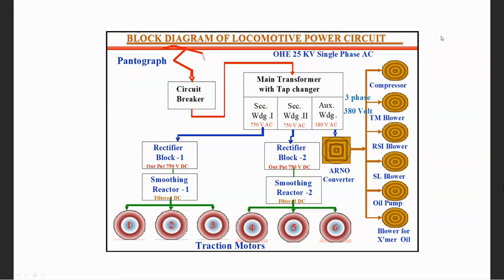This is the block diagram for the locomotive. The OHE pantograph power supply comes as 25 kV and is passed to the primary side of the transformer. We have two secondary windings. One secondary winding is connected to one rectifier block and its associated smoothing reactor, and the power supply then goes to three traction motors provided in one bogie, assuming it's a CoCo kind of locomotive. So one secondary winding takes care of one bogie's traction motors. A similar arrangement is available for the other secondary winding.